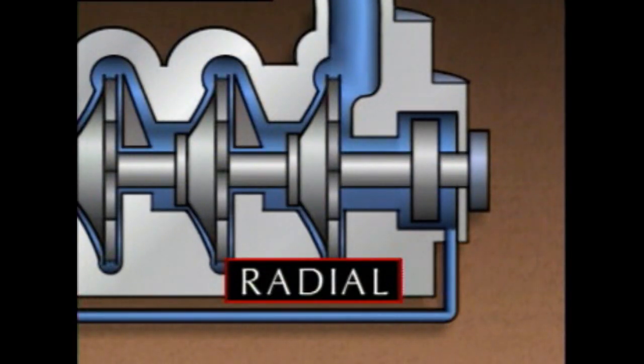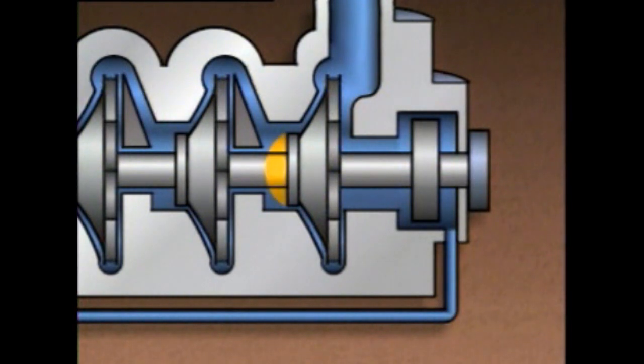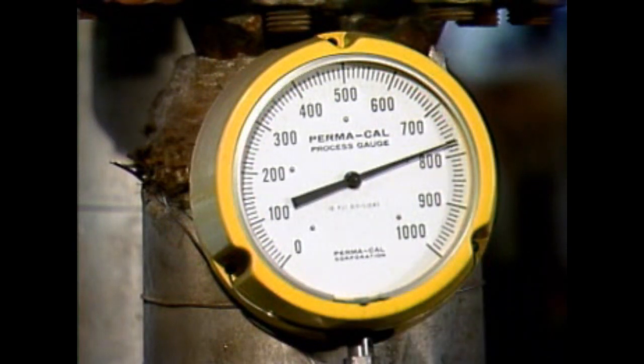One way that centrifugal pumps can be categorized is by the way liquid flows through them. Three common flow path classifications are radial flow, axial flow, and mixed flow. In centrifugal pumps with a radial flow design, the impeller causes the liquid to make a 90-degree turn and flow outward, or radially, from the suction eye to the tips of the vanes. A radial flow pump takes advantage of the maximum amount of centrifugal force the impeller develops. Generally, radial flow pumps are capable of higher discharge pressures, but they don't move as much liquid as other types.